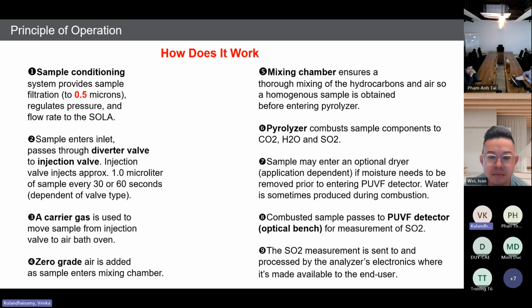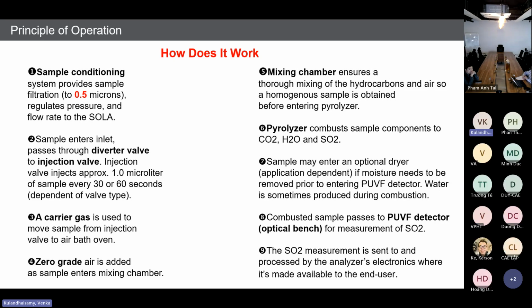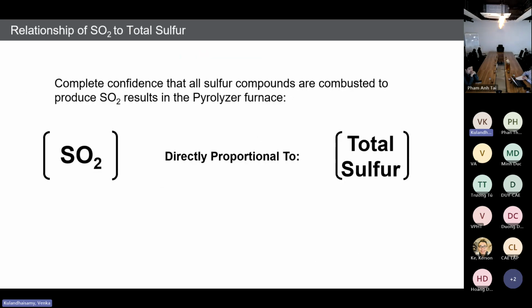That light energy is captured by a photomultiplier, then the photomultiplier converts the light energy to a current, meaning milliamps or voltage. Okay, finally, the voltage or milliamps is converted to ppm. So how much energy we receive, that energy is equal to your total sulfur. Okay, so we have complete confidence that all sulfur components are combusted to produce SO2 in the pyrolyzer furnace. So SO2 is directly proportional to total sulfur.